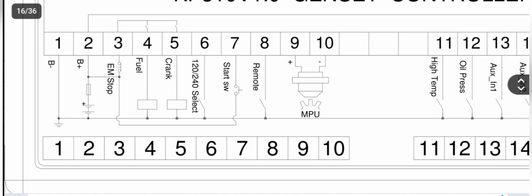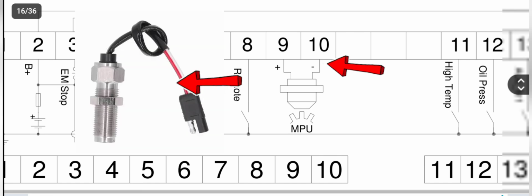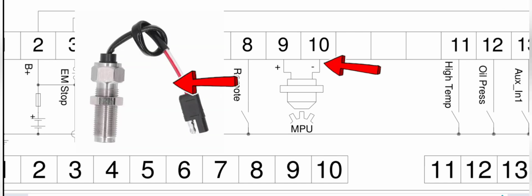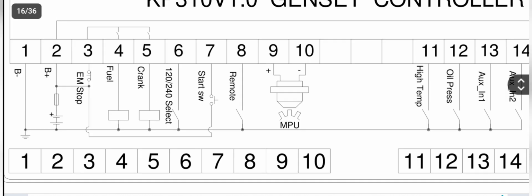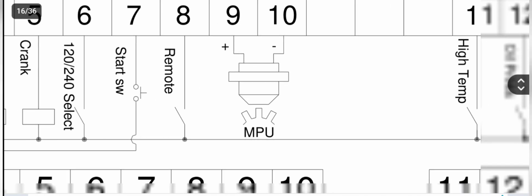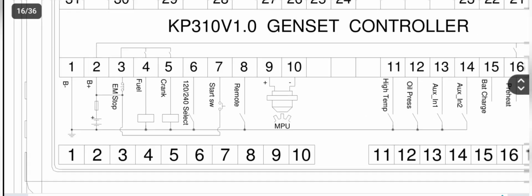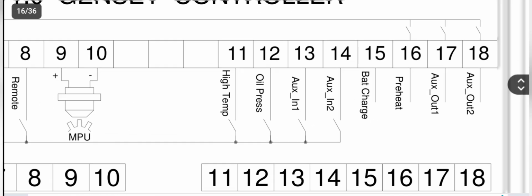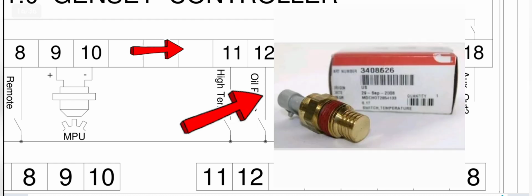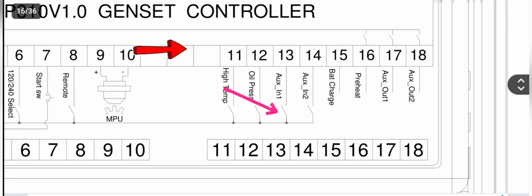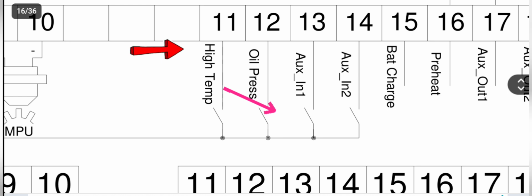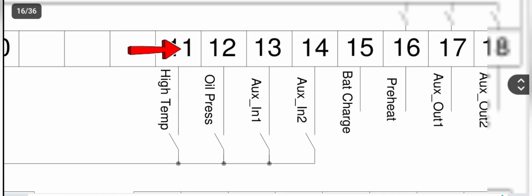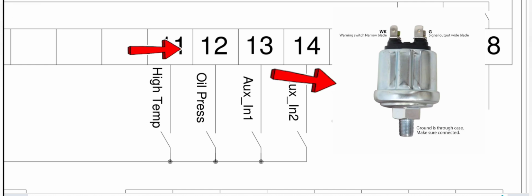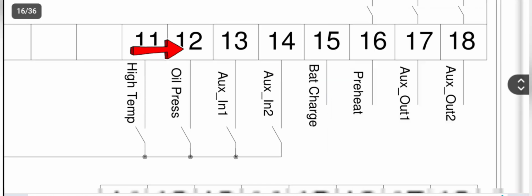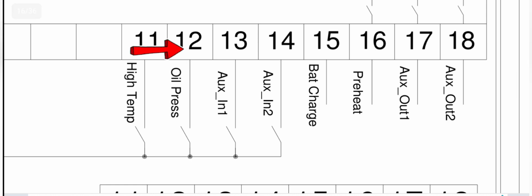Okay, after that, 9 and 10 are the MPU input, negative and positive. MPU means the magnetic pickup unit, or simply called a speed sensor. Pin 11 is our high temperature switch. It's also connected with the ground side: one side is the ground side, one is the input to pin number 11. Pin number 12 is the oil pressure switch input. Pins 13 and 14 are auxiliary inputs, you can use them for another purpose.